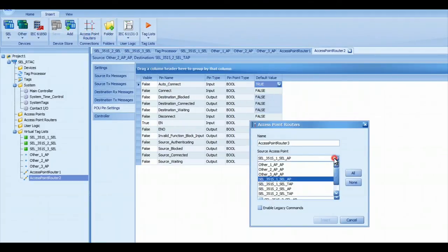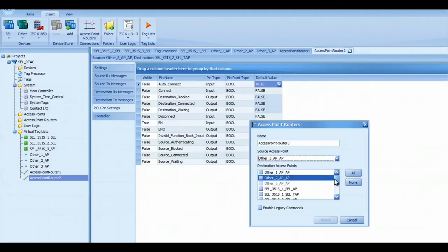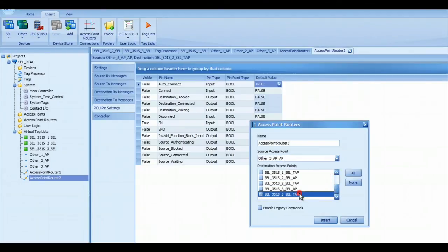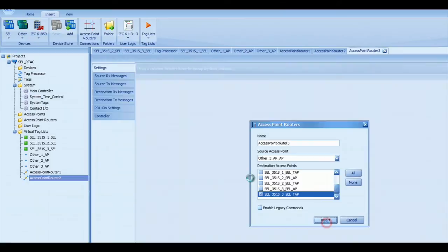And that way, you don't have to do the legacy port commands. As soon as you connect to the RTAC, the RTAC will automatically connect you to the relay. There's no source authentication like we did before, but that's okay if this is the way that you want to do it, because you can log into the relay and use the relay's authentication.